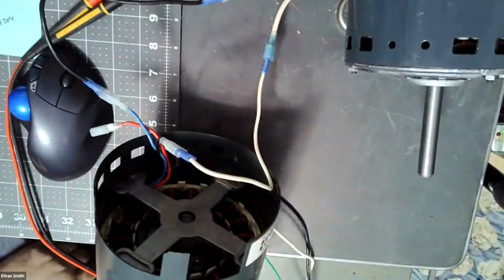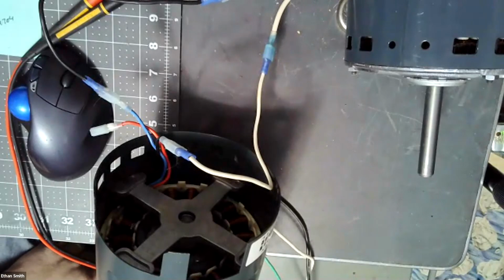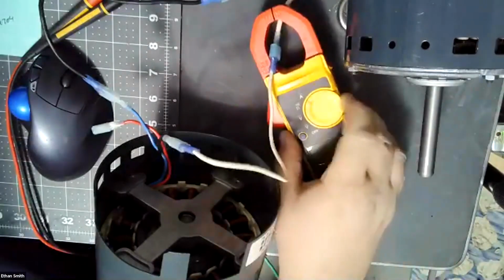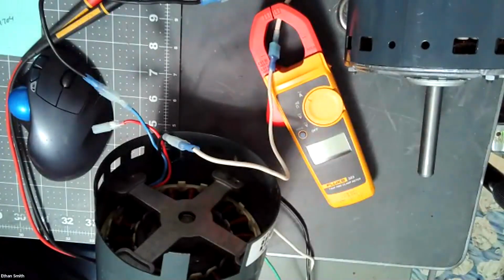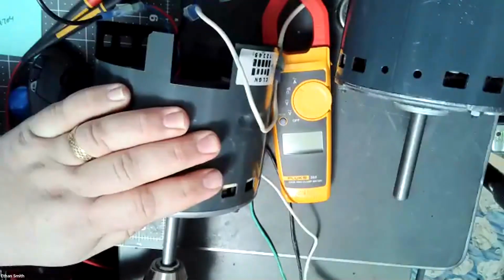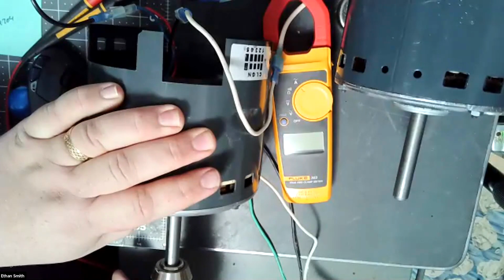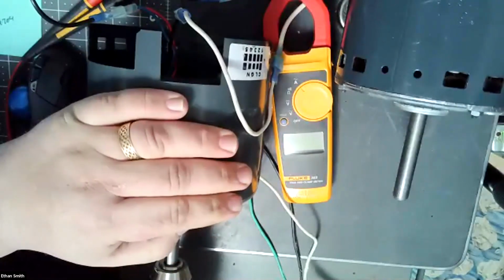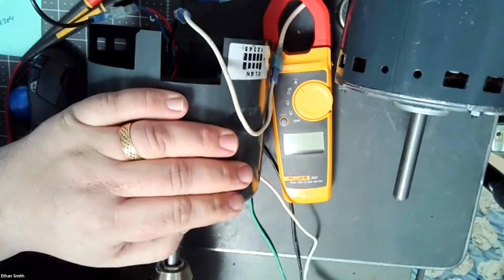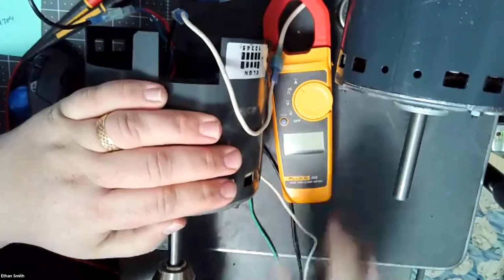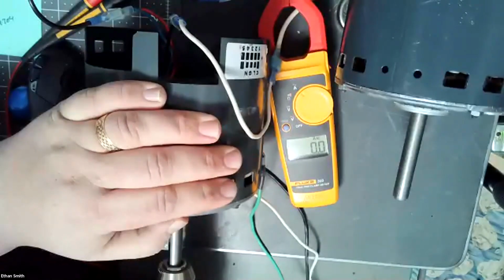What do you guys think is going to happen if I turn on this generator here? It'll run, but the hertz is going to be something different, maybe. Yeah, so this is designed to be run off of 60 hertz and 115 volts. What was my frequency at the top end, guys? Anybody remember? Wasn't it like 220 or something? And then the voltage was way high too. So we're going to run high frequency, high voltage, and let's see what happens. I'm going to put my amp meter here just to see how many amps we're going to draw. And here we go.